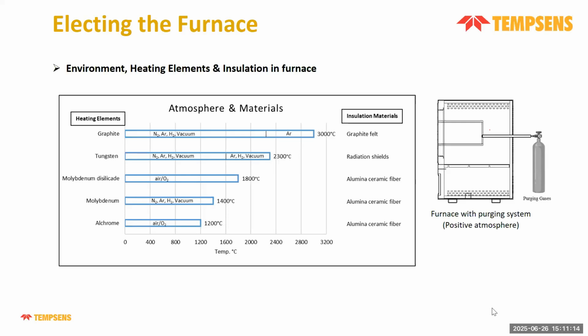And the third one is the heating element. What kind of heating element we choose depends on the temperature and the atmosphere. If the temperature is 1200 degrees centigrade under air or oxygen atmosphere, we can use the Alchrome wire, basically FeCrAl wire. For 1400 degrees centigrade, if your environment is nitrogen, argon, hydrogen or vacuum, we have to use molybdenum. For air and oxygen, up to 1800 degrees centigrade, we use the molybdenum disilicide heating element. For 2300 degrees centigrade in argon, hydrogen or vacuum, we use tungsten or tantalum heating elements. And for 3000 degrees centigrade, in nitrogen, argon, hydrogen and vacuum, we use graphite. And these are the insulation materials listed as per the heating elements.